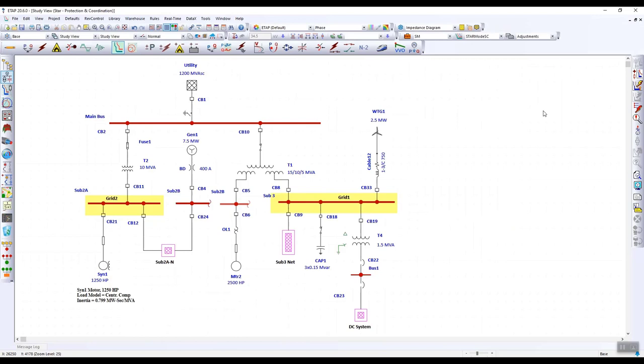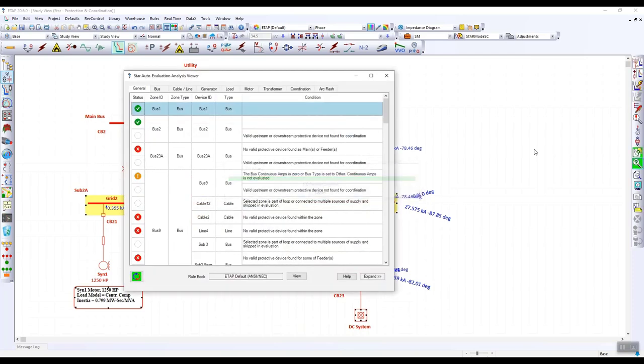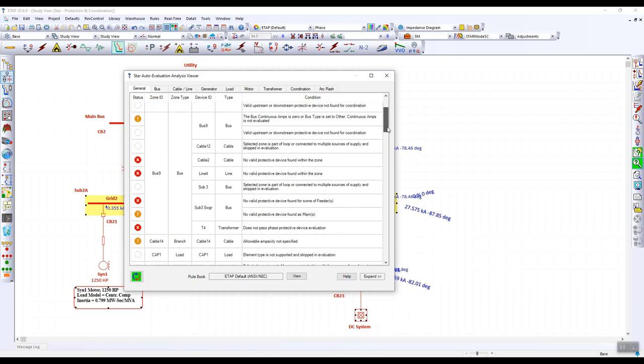If we'd like to verify that our protection and coordination meets our customized design criteria or industry guidelines like the NEC handbook, we can run Star Auto evaluation for the entire project or a portion of the project and verify that it meets these guidelines. The green check marks mean that we passed the evaluation based on the selected rules. The red X's mean that we failed in the evaluation due to a violation from the rules. The orange exclamation points mean that we observed conditions which need attention as they may change the results. On the right hand side, we are showing the condition for the status of that device.